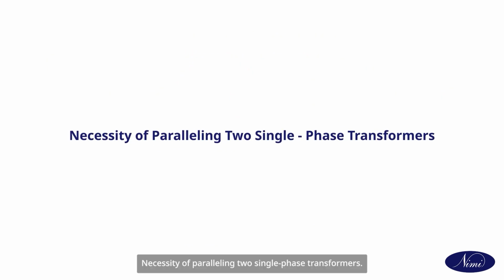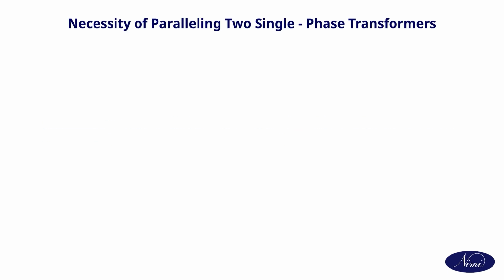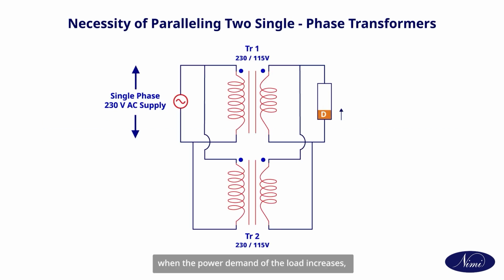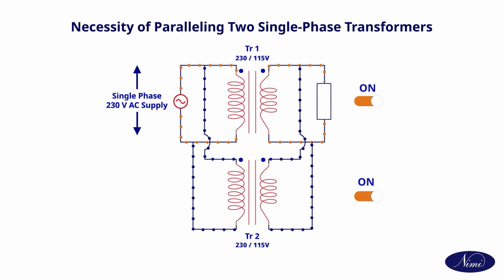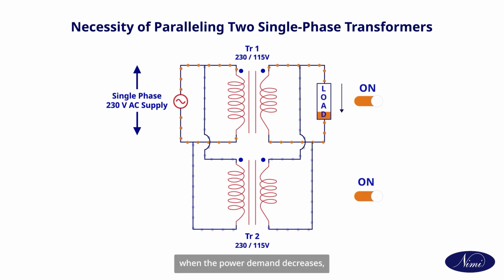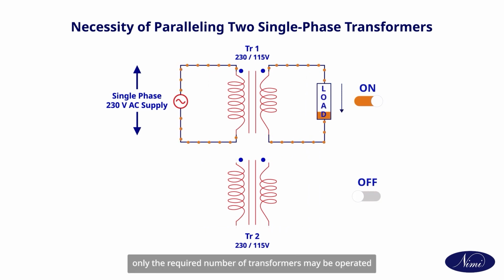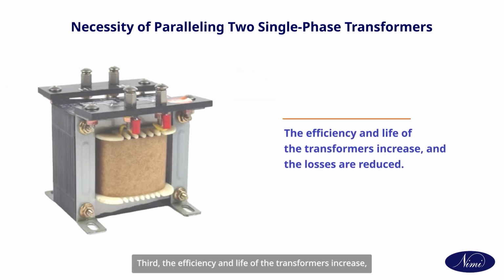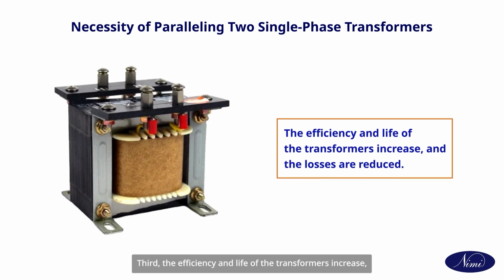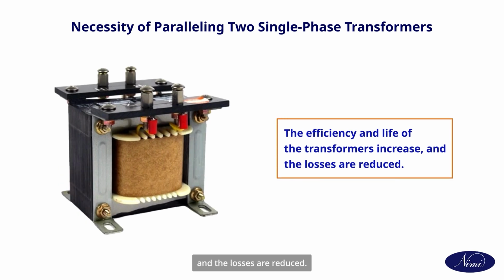Necessity of paralleling two single-phase transformers. First, when the power demand of the load increases, two or more transformers may be operated in parallel. Second, when the power demand decreases, only the required number of transformers may be operated with their full load capacity, whereas the remaining transformers may be switched off and taken for general maintenance or service. Third, the efficiency and life of the transformers increase and the losses are reduced.